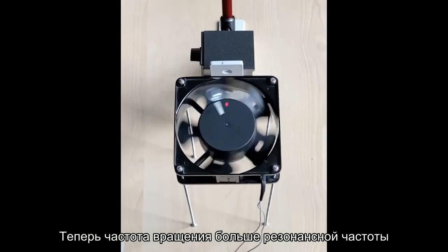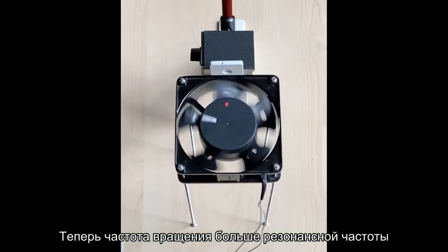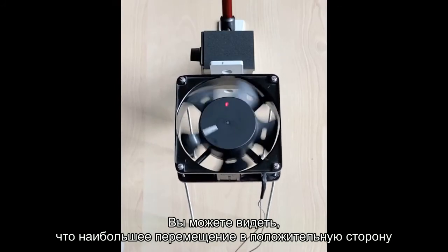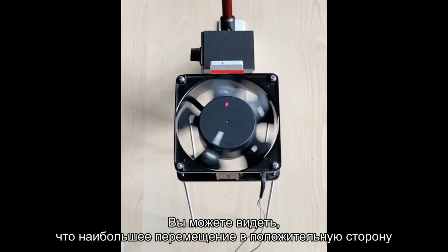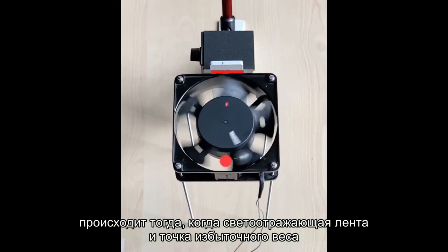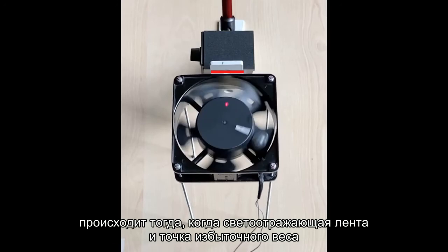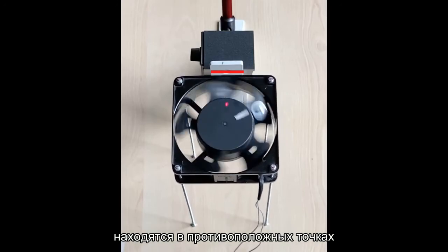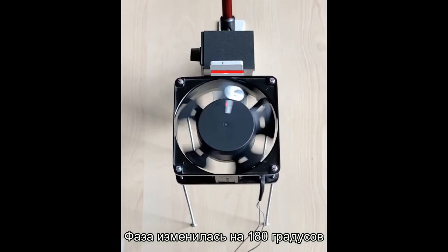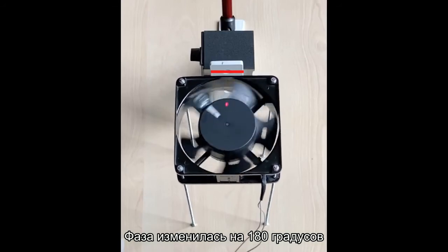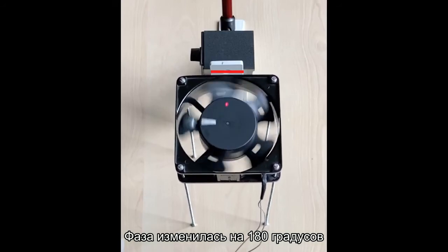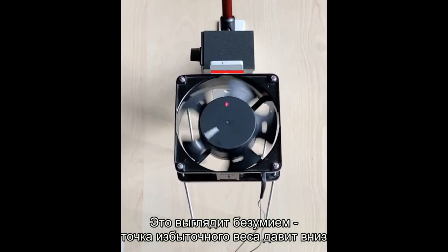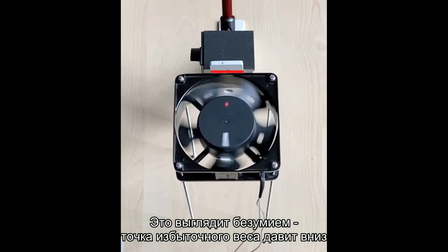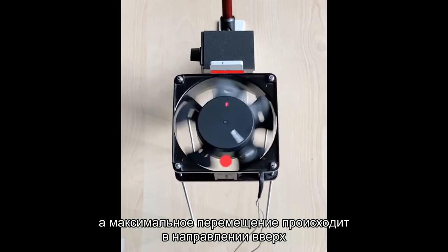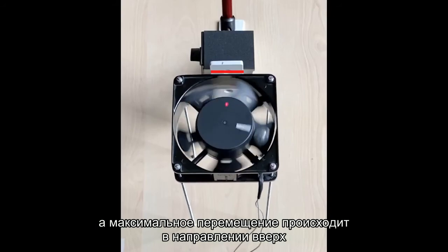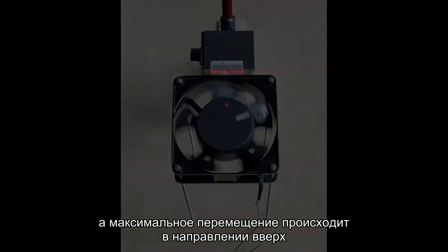Now the speed is higher than resonance frequency. You can see that the highest positive displacement occurs when the reflective tape and the heavy spot are on the opposite side. The phase changed by 180 degrees. It looks crazy. The heavy spot pushes down and the maximum displacement occurs in up direction.